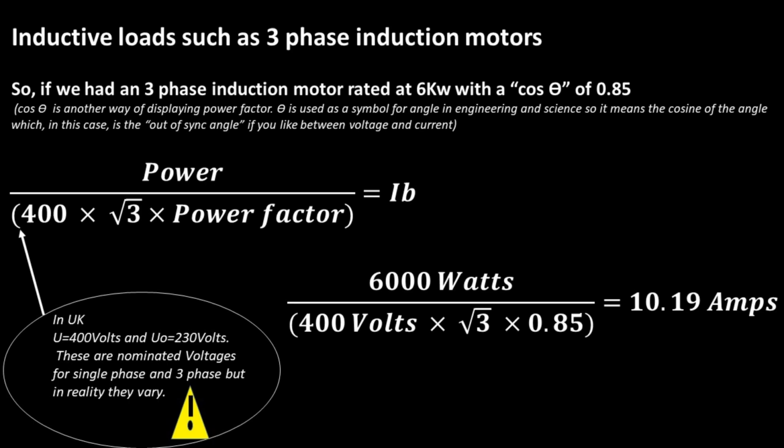So 400 times root 3, what's all that about? Well, it's to get essentially three single phases, but it's not quite accurate enough if you just do 230 volts times 3, and that's all down to the sine waves, and I'm not going into that on this video. So it's 400 times root 3 times power factor.